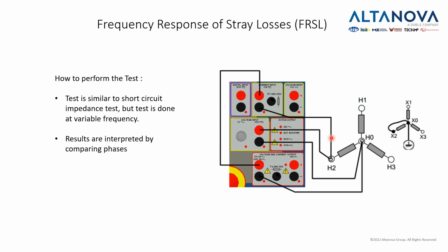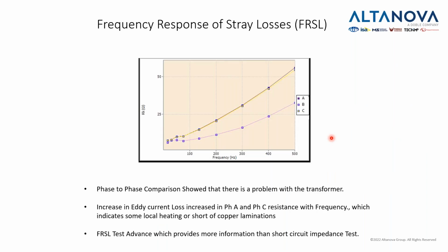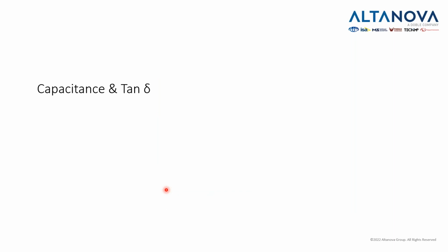We need to compare phases in order to interpret these results. And in this particular case, we see that one phase, phase B, is not like phases A and C, which will lead us to believe that this transformer might have an increase in eddy currents. So this is the frequency response of stray losses.